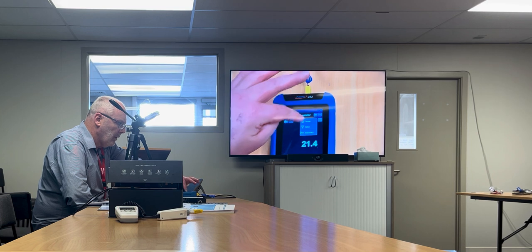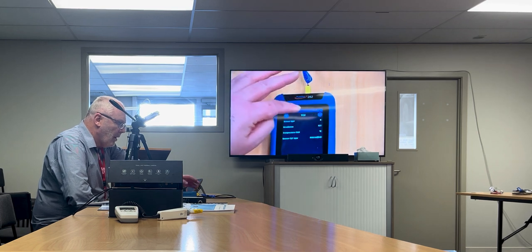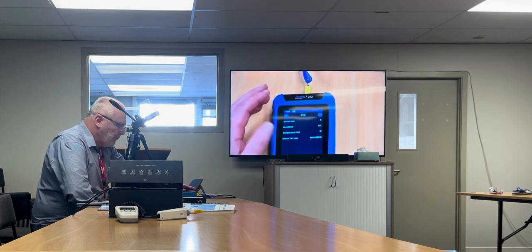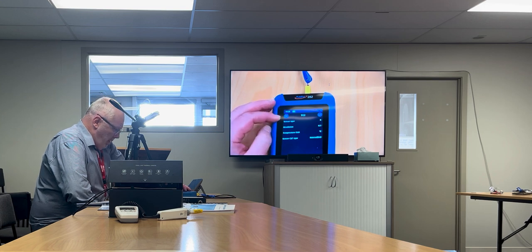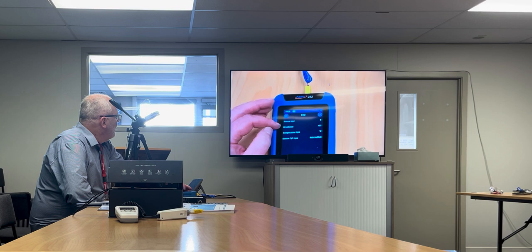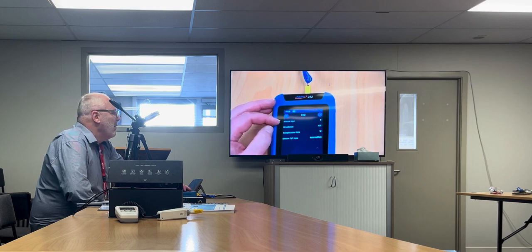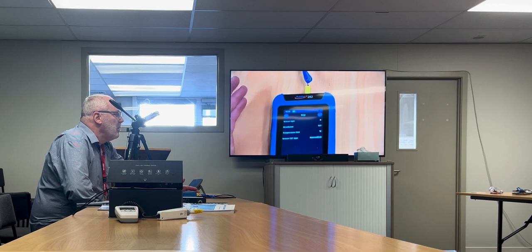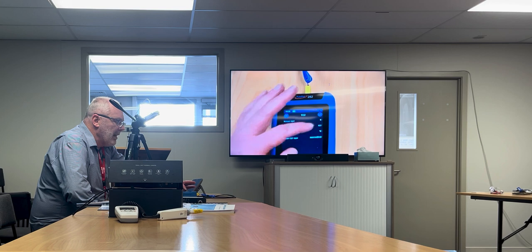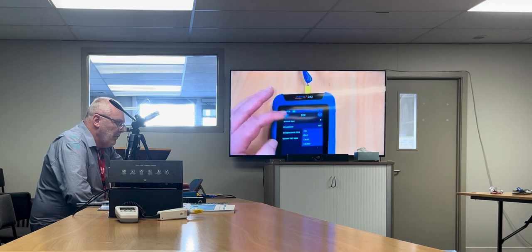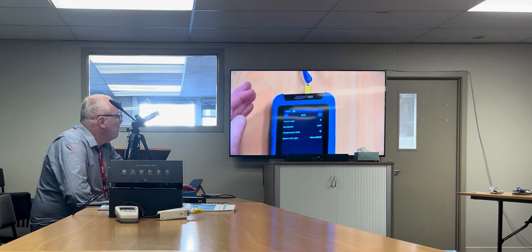Oh, while we're there - so this is your setter. You can adjust the fine tuning, so for K-type thermocouple, the resolution. Normally you're not going to have any better than 0.1 resolution on a thermocouple, but you might for some reason, especially if you're using something fancy like an R or an S. So you could make that 0.01 if you wanted to.